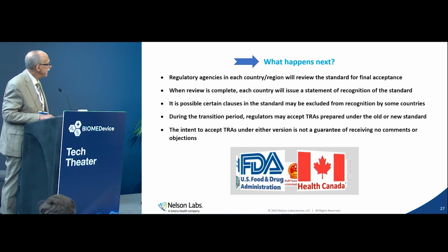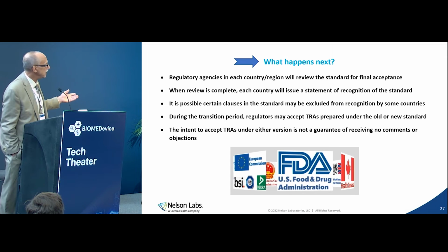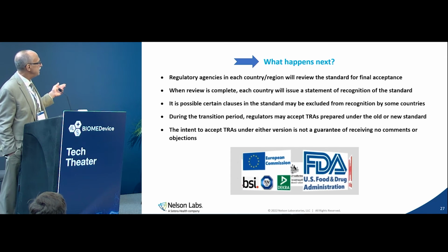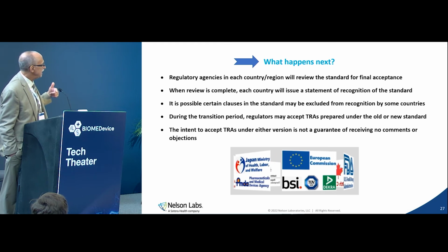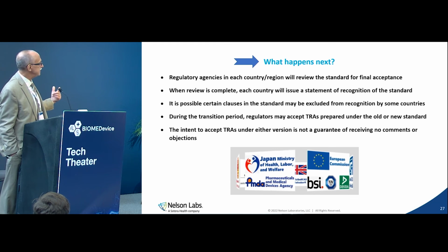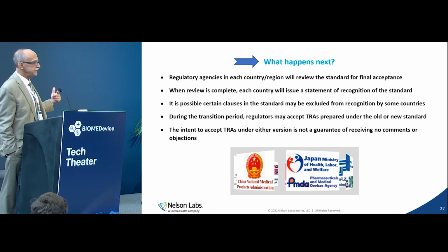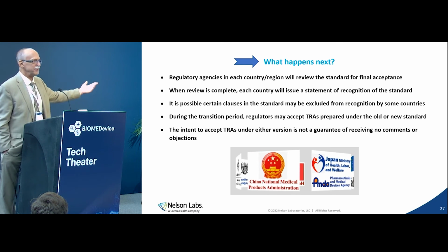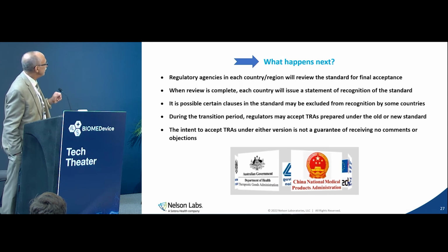What happens next? Regulatory agencies will review this standard. Remember, it just came out 7 days ago. When the review from each country or region is complete, they're going to issue a statement of recognition. It's possible that certain clauses in the standard might be excluded from recognition by some countries. Hint, hint, FDA. FDA never accepts everything without saying, no, we don't buy this. So we'll have to wait and see.